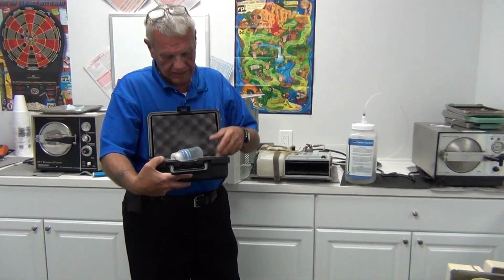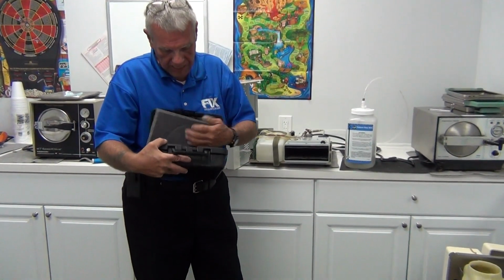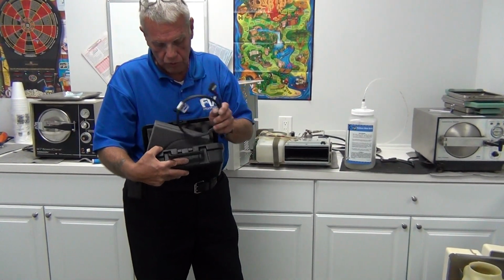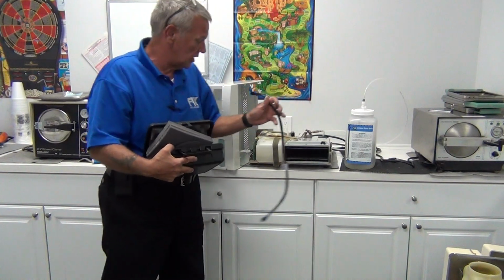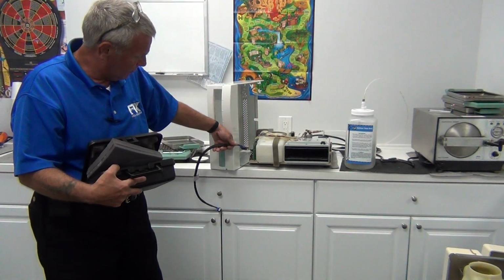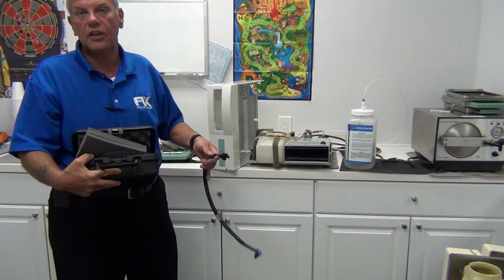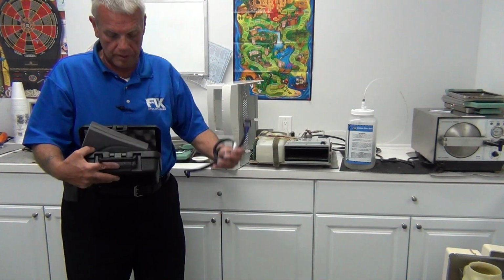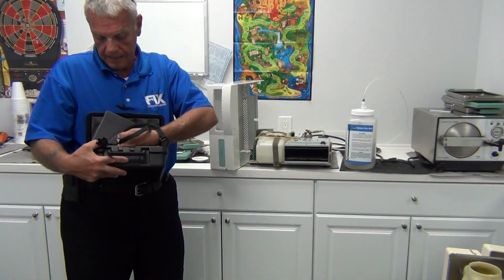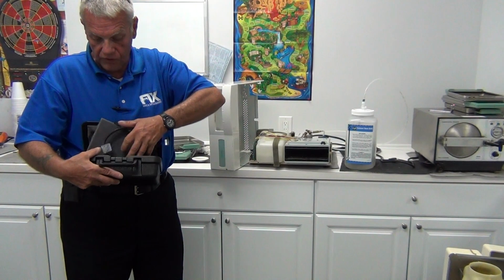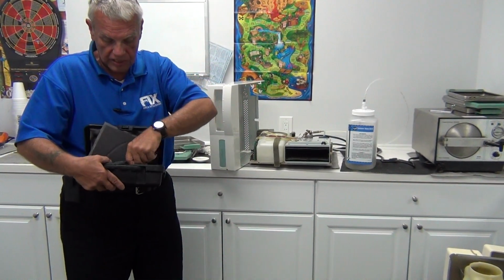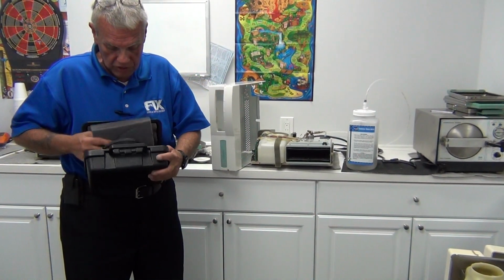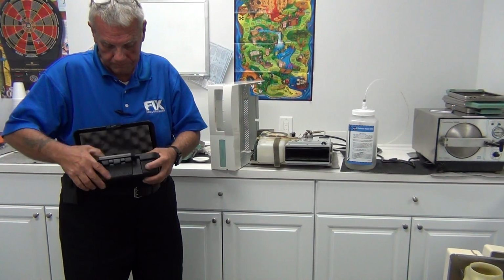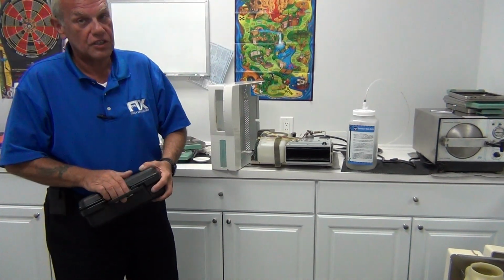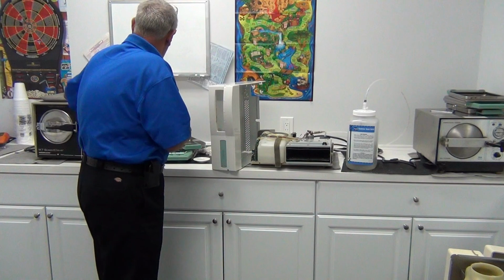Now you can buy a calibration kit at Dental Fix that has longer extension cables in it. If you do have to get into servicing the machine, you use the longer cable, and it allows you to put the cover at a further, more remote location. I would strongly advise, if you've got a lot of Statims in your territory, to go ahead and purchase the calibration kit. Again, it's available at parts at www.dentalfix.com.